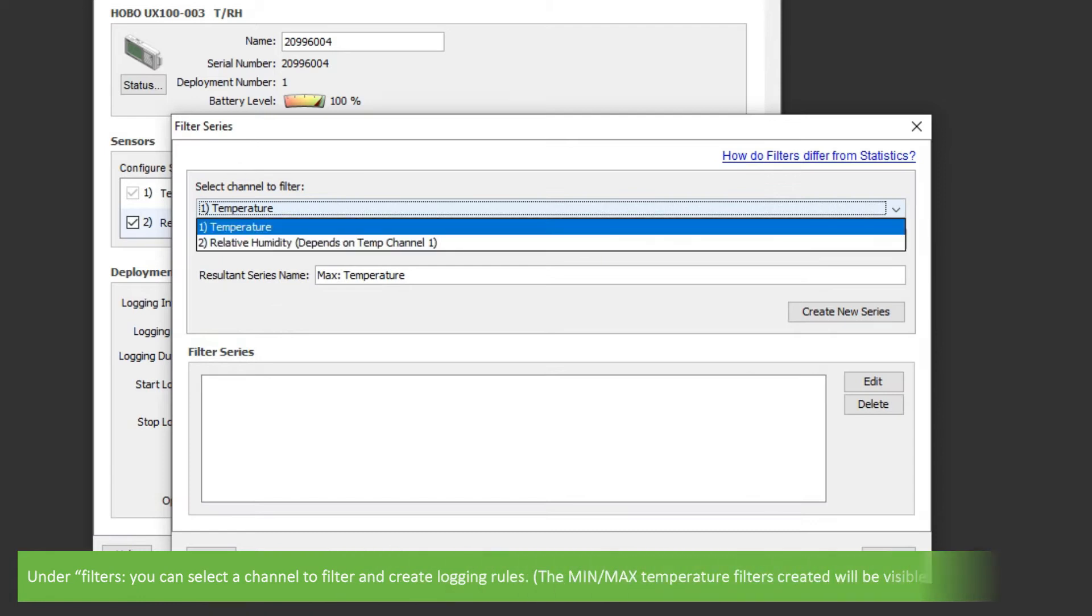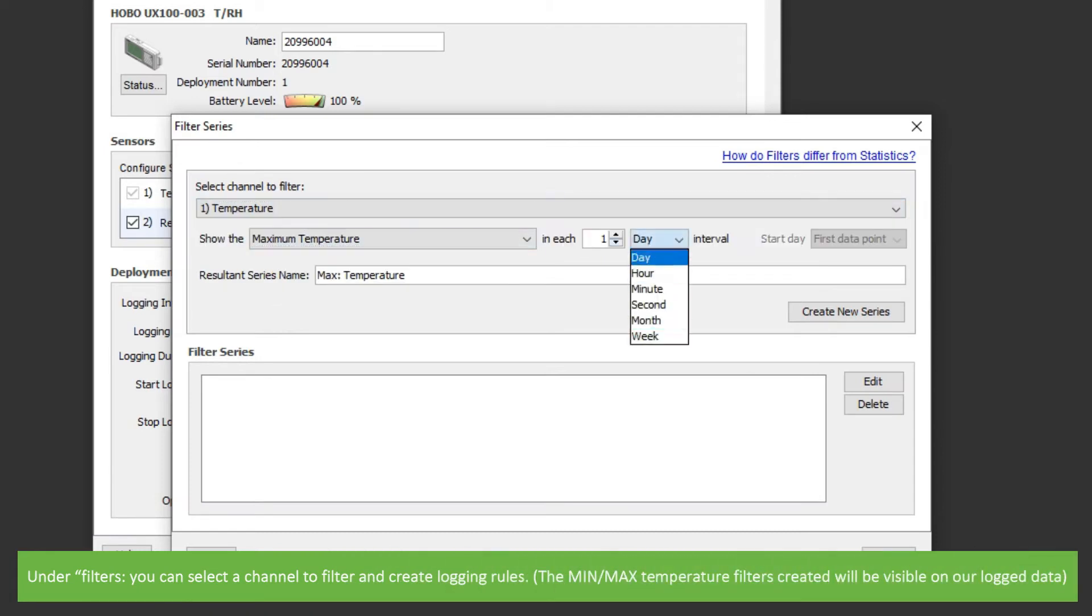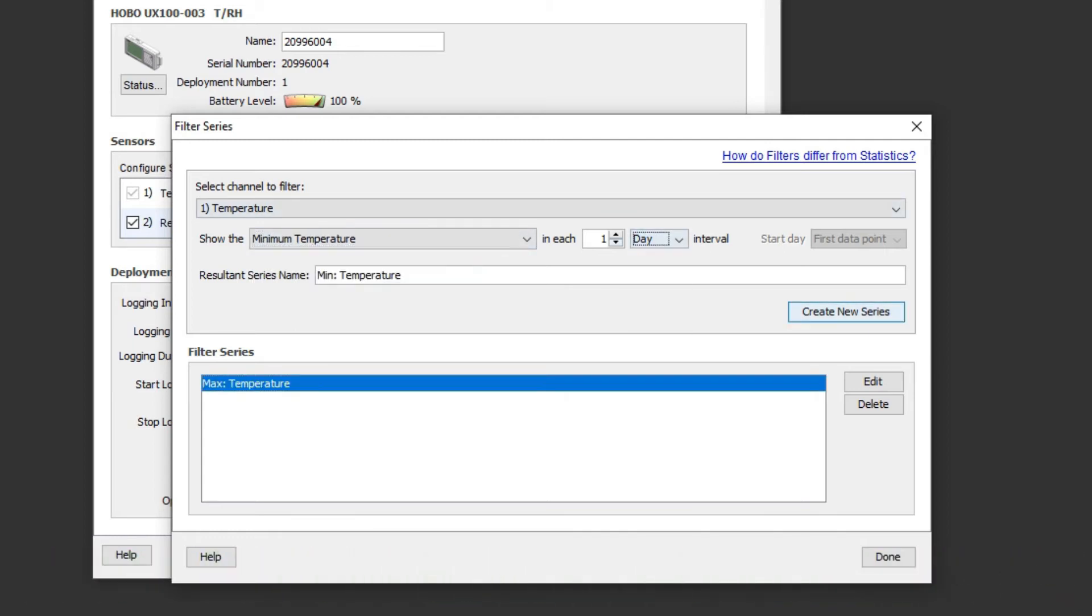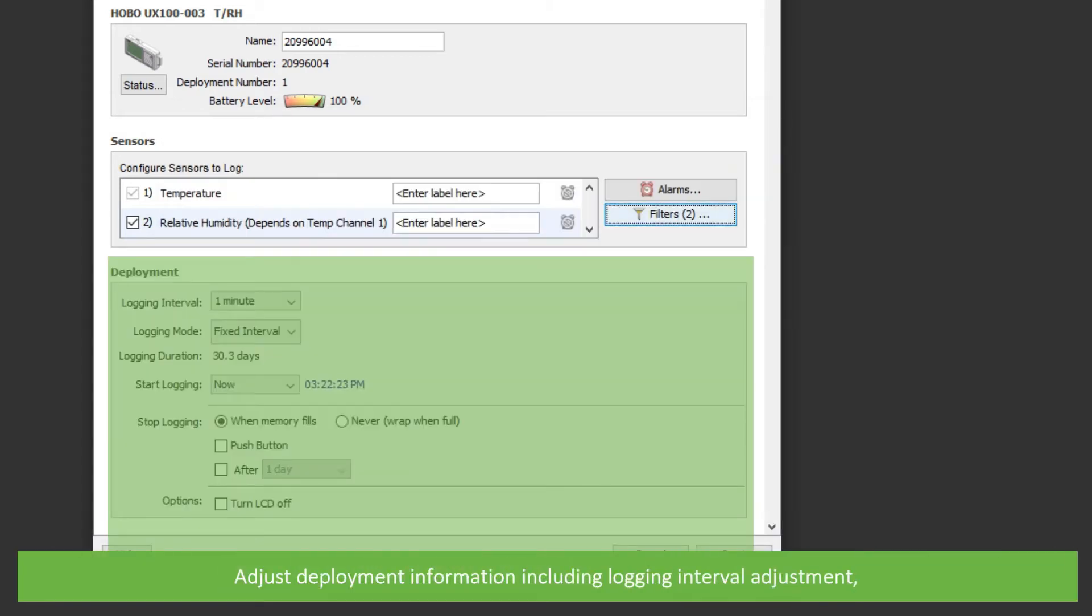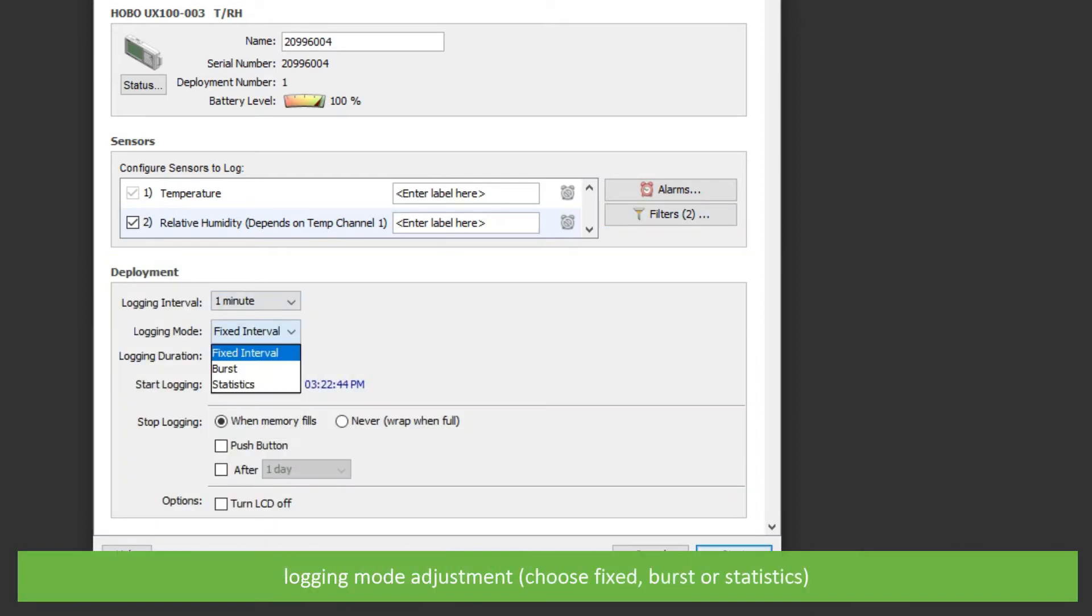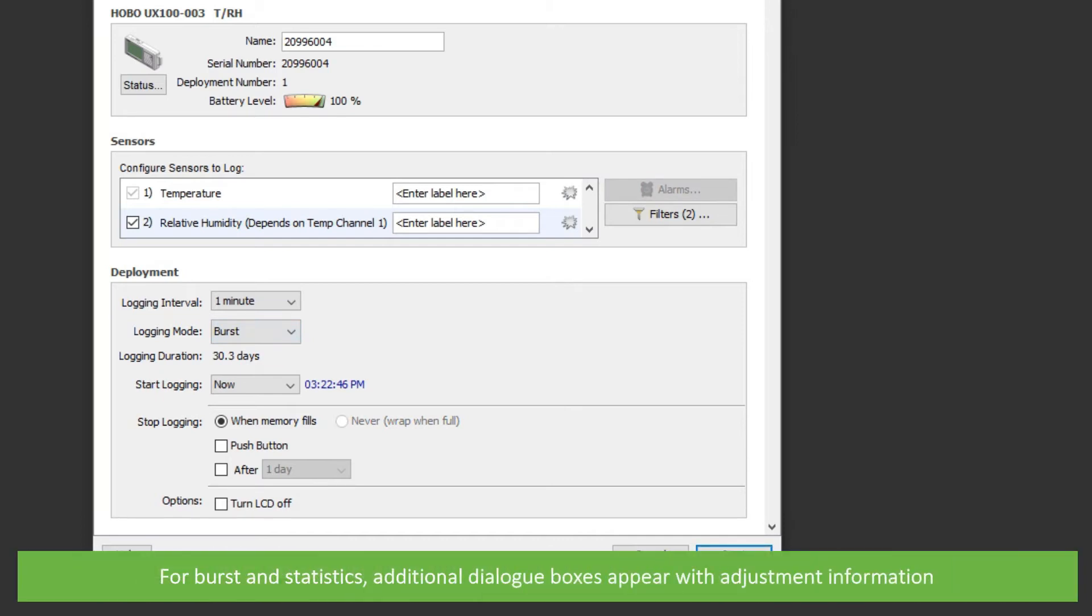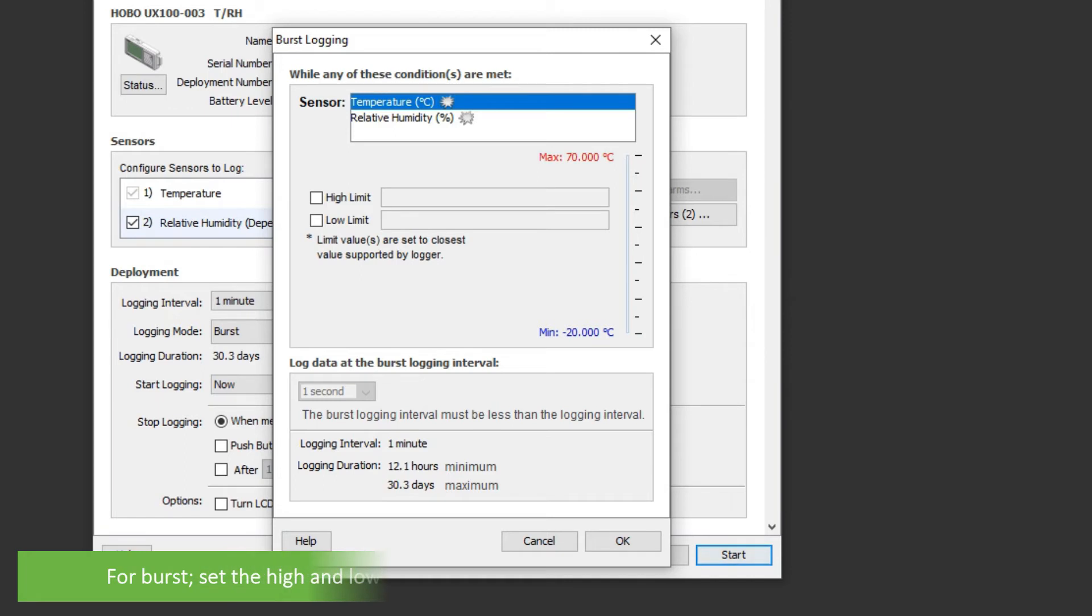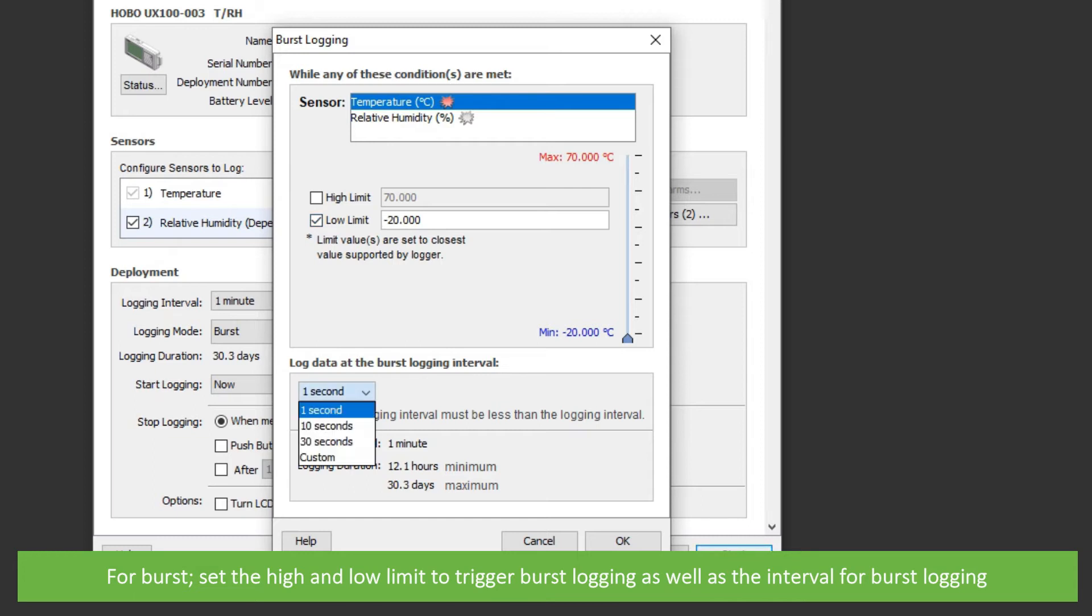Under filters, you can select a channel to filter and create logging rules. Adjust deployment information including logging interval adjustment. Logging mode adjustment. You can choose between fixed, burst or statistics. For burst and statistics, additional dialog boxes appear with adjustment information. For burst, set the high and low limit to trigger burst logging, as well as the interval for burst logging.